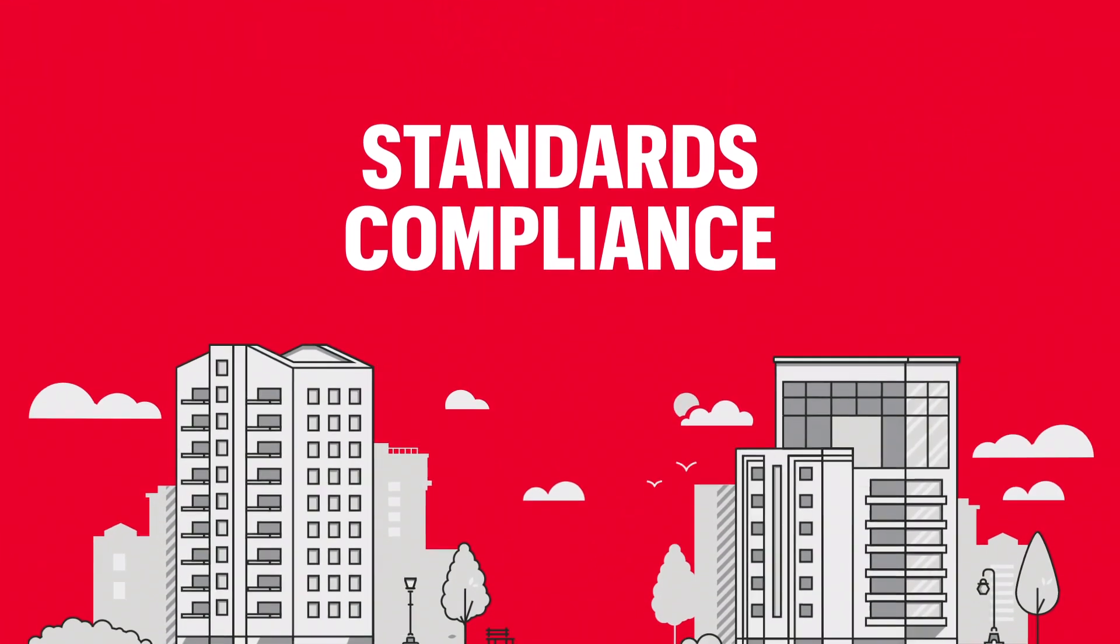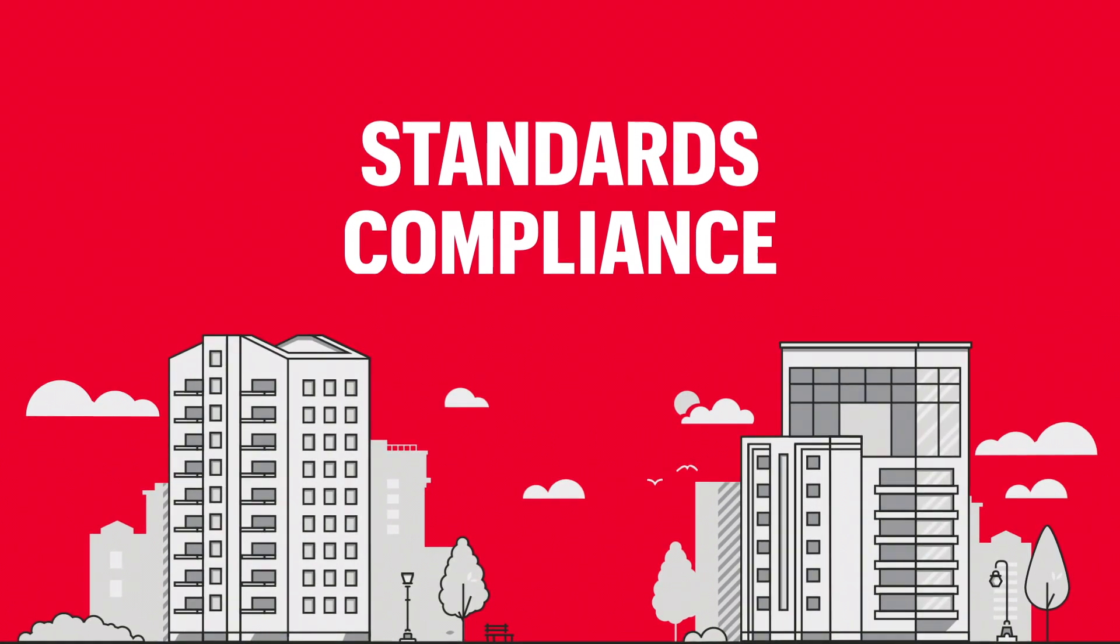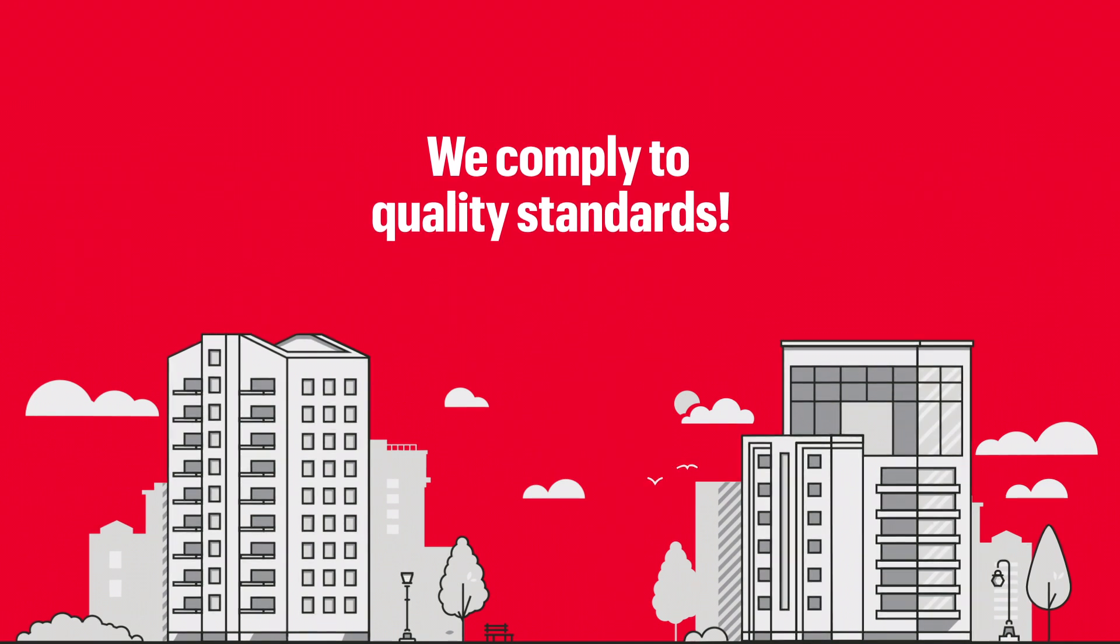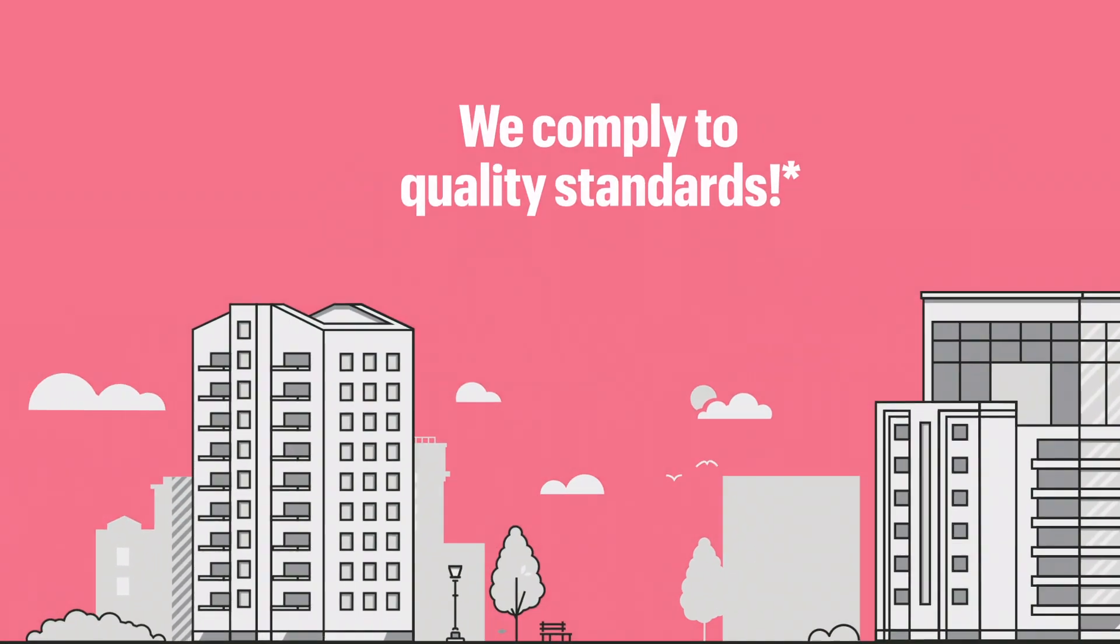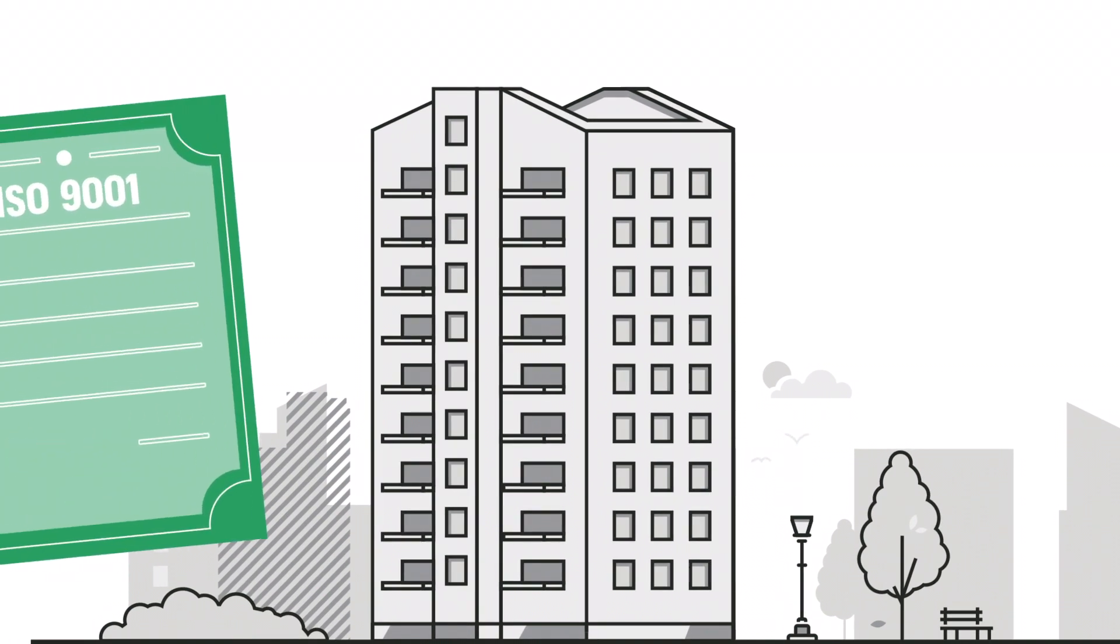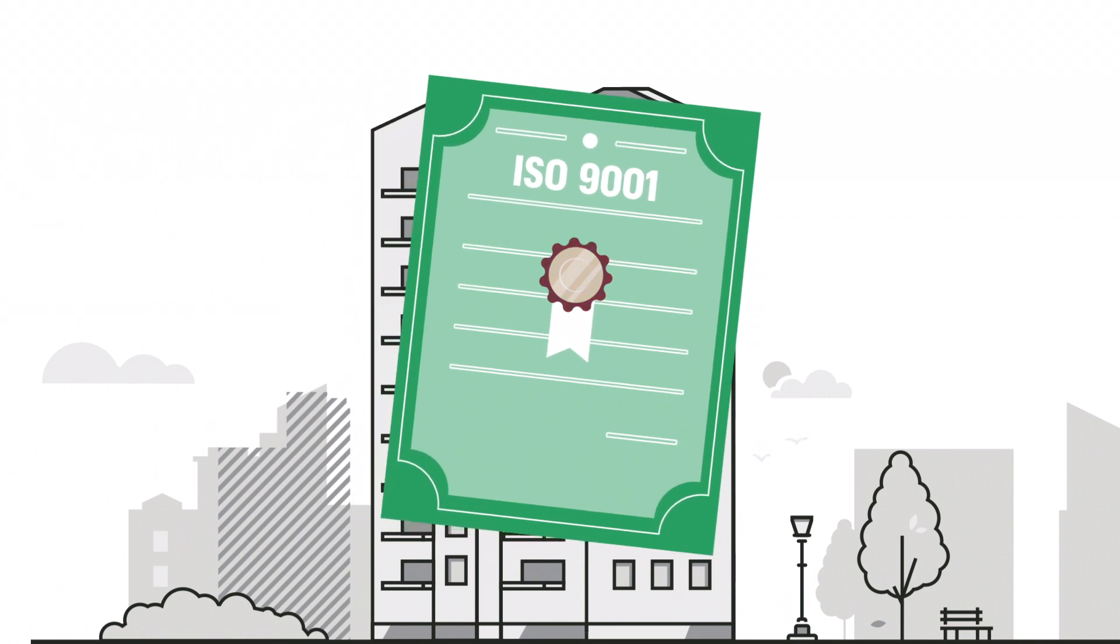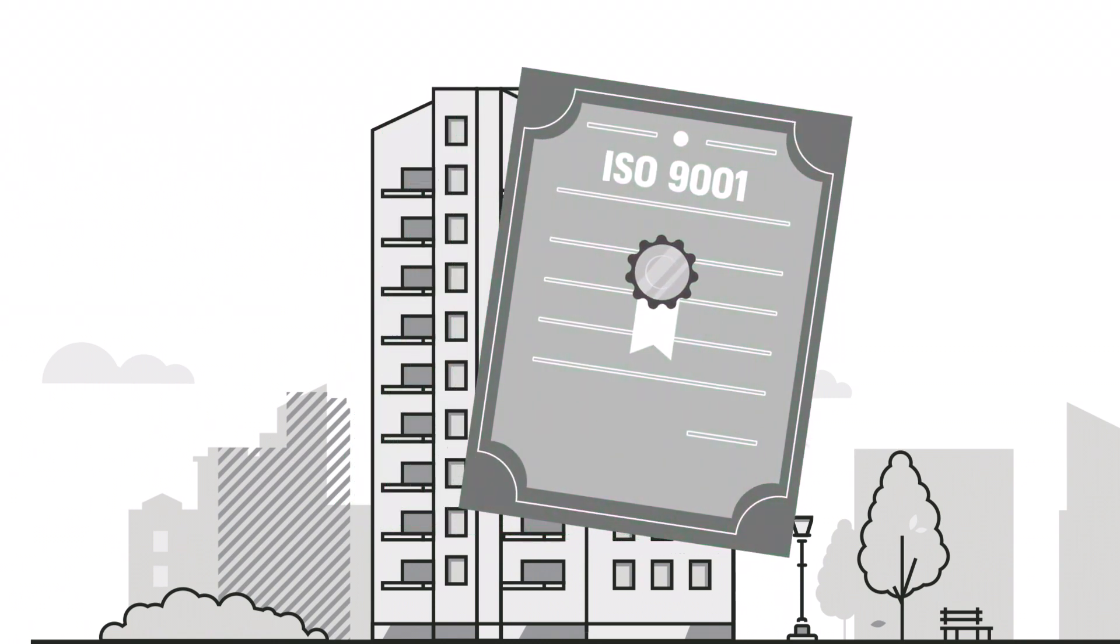Compliance to global calibration standards, such as ISO 17025, ensures the competence of calibration labs. Yet many labs make blanket marketing claims well beyond their actual compliance. By the way, if the primary quality claim of a calibration lab is to ISO 9001, that's inadequate to ensure lab competence.